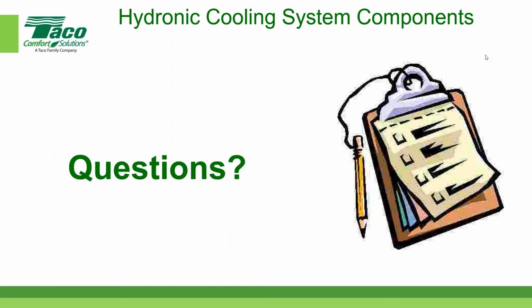What's your comment on shutoff valves? Can't have enough of them? I can't have enough of them. I mean, if you have a system that's got 10 shutoff valves, I want it to have 20. So yeah, the more isolation that you can do, the better you're going to be in terms of service and maintenance. And so some people say, well, I don't want to put in a lot of isolation valves because it creates pressure drop. Well, most of the smaller piping, if you go with full port ball valves, the pressure drop is negligible.